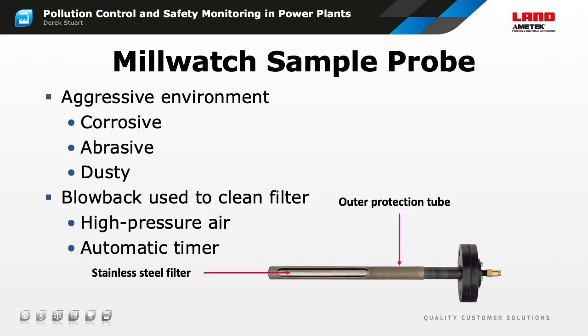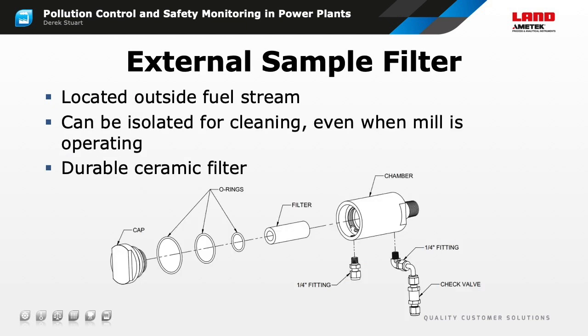The AMETEK Land mill probe is specially designed to withstand the aggressive environment at the mill outlet. It has a large area stainless steel filter to resist blockage, a blowback facility for self-cleaning, and a hardened steel abrasion shield to protect the filter from impact from the high concentration of high-velocity coal dust passing through the mill outlet. An alternative sampling device is available for applications where it's undesirable to have a probe penetrating into the sample stream. For example, where the sample has to be drawn directly from the mill body rather than the classifier outlet.